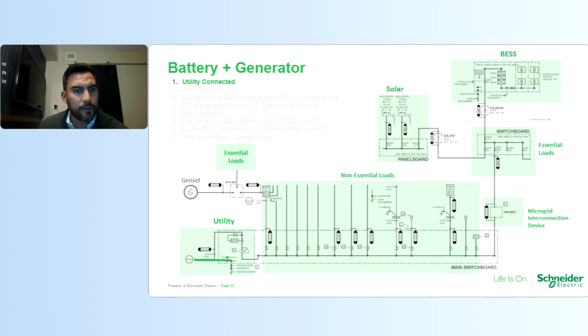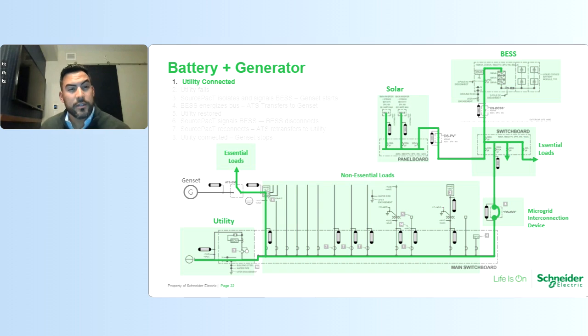Here, this is for a K through 12 facility where they had an automatic interconnection switch. You can see off of the main switchboard, the first breaker to the left is connected to a transfer switch, which is connected to their own essential loads. We call these essential loads because we don't want to specifically reference them as emergency loads. They could be legally required loads. We really just recommend the consultant or client to define what those loads are.